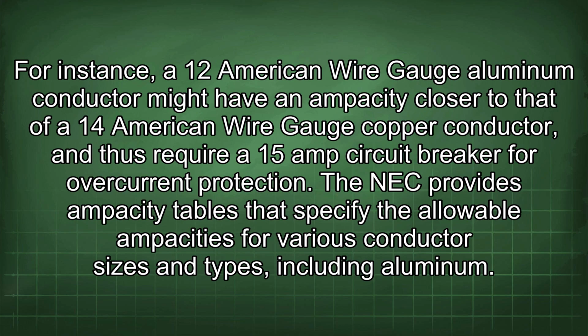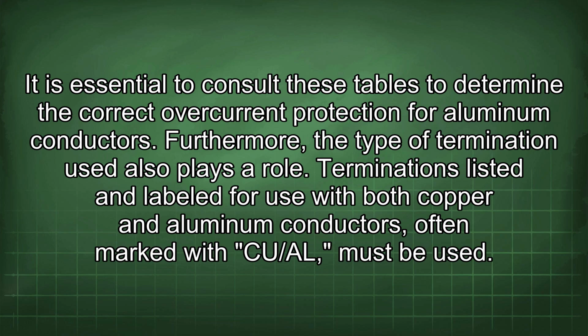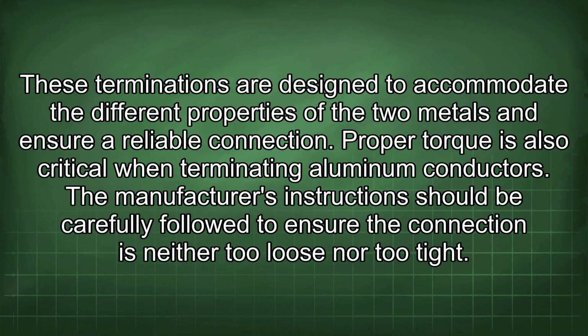The NEC provides ampacity tables that specify the allowable ampacities for various conductor sizes and types, including aluminum. It is essential to consult these tables to determine the correct overcurrent protection for aluminum conductors. Furthermore, the type of termination used also plays a role. Terminations listed and labeled for use with both copper and aluminum conductors, often marked with CU/AL, must be used. These terminations are designed to accommodate the different properties of the two metals and ensure a reliable connection.